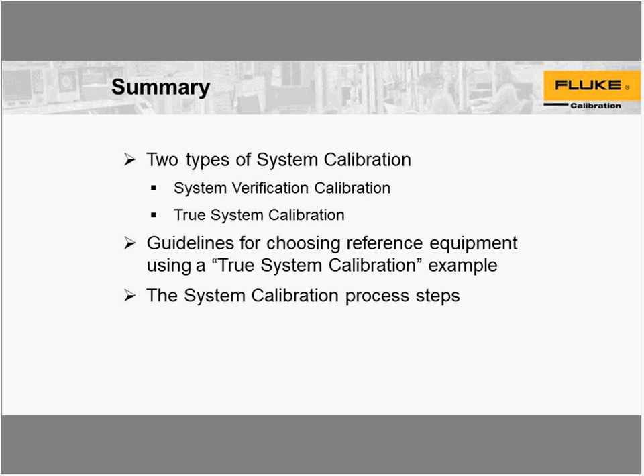Okay, we don't put all the baths that we use on the calibration certificate because we're not trying to transfer a calibration from a bath to your equipment. That's heat source only, and we're transferring the calibration from the reference probe to your system. That's the way it would work. There's no need to list a heat source unless you're using the display from the heat source as your reference, and then it defeats what we're doing using a reference thermometer.